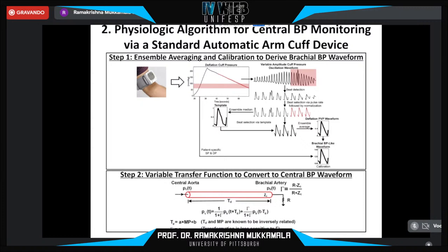So what happens is we derive the brachial blood pressure waveform, compute the mean value of this waveform, and that determines the pulse transit time parameter of the transfer function. Then we apply the transfer function to this waveform to get the central blood pressure waveform, and from that waveform we can detect the peak and the minimum to get the central systolic and diastolic pressure.